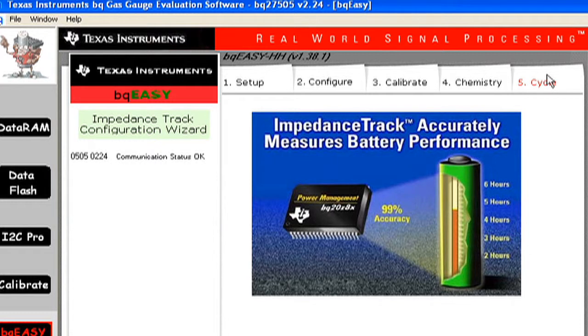How long might this process take you? Although it's a wizard, it's not really magical, and we are limited by the physical reality of charging and discharging the battery. At a minimum, this may take several days, but I recommend you budget about a week in case there are any hiccups and you have to restart any of the cycling processes.